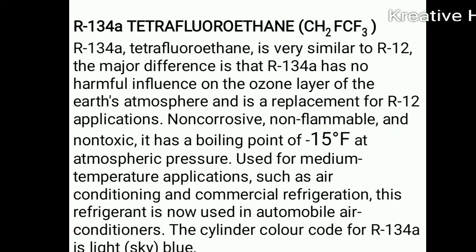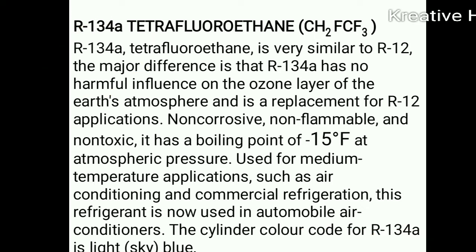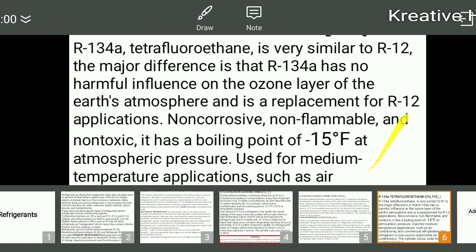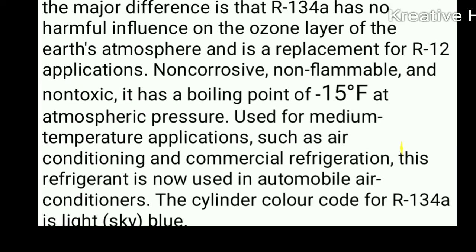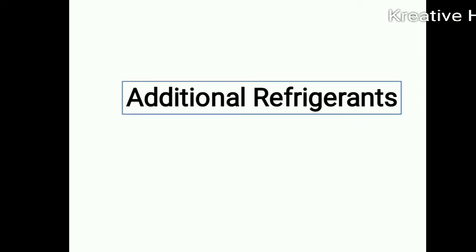R134a is tetrafluoroethane, similar to R12. The major difference is that R134a has no harmful influence on the ozone layer, making it a replacement for R12. It is non-corrosive, non-toxic, and applicable for medium-temperature use such as air conditioning and commercial refrigeration. The boiling point is minus 15 degrees Fahrenheit at atmospheric pressure. The cylinder color code for R134a is light sky blue.